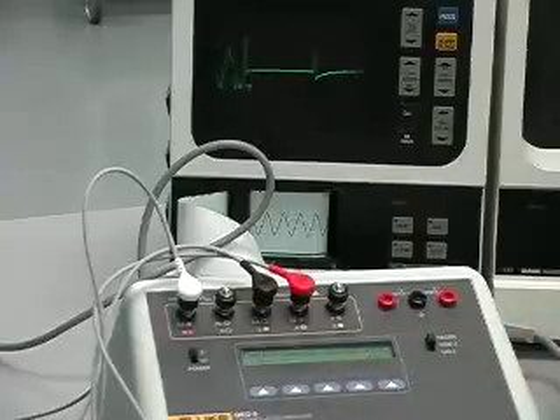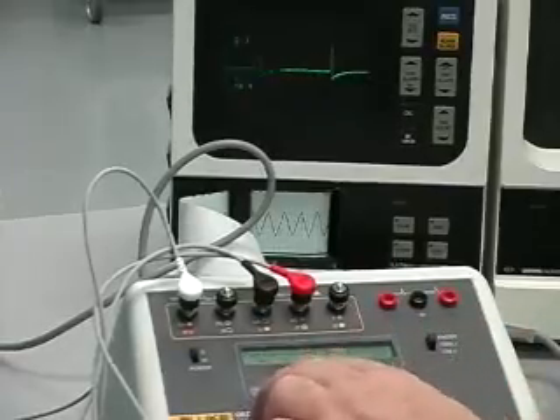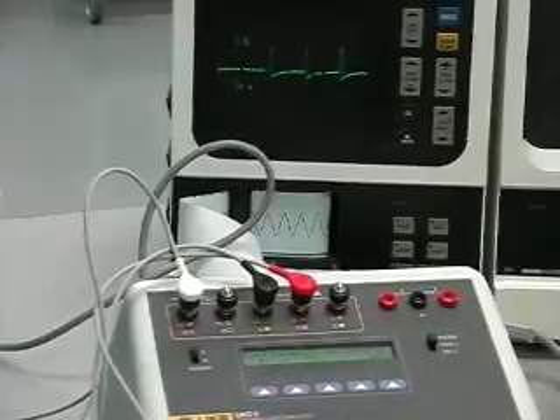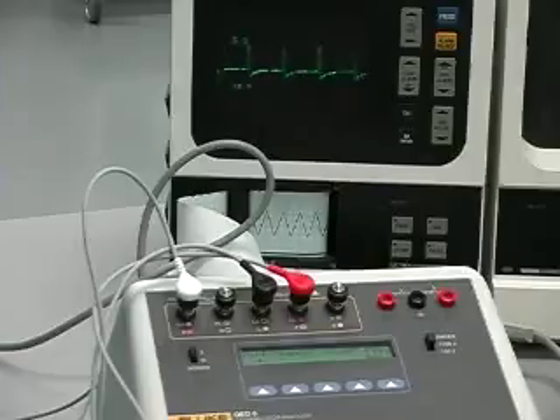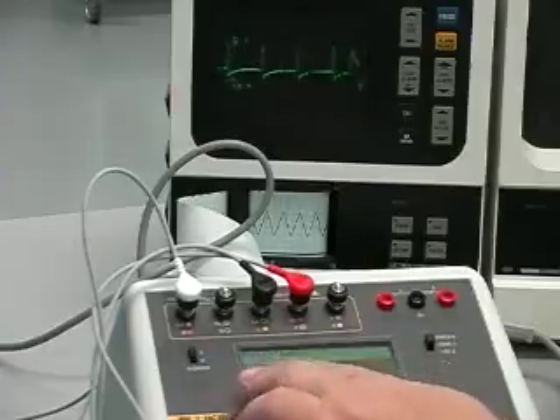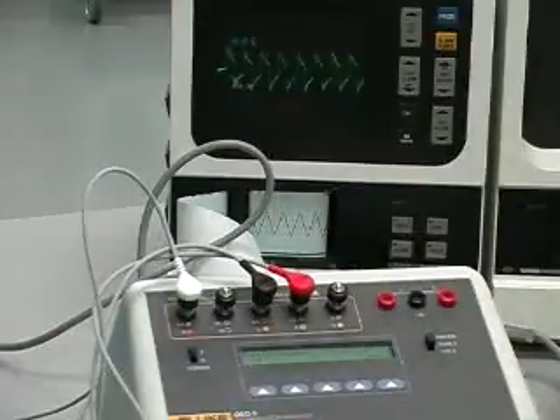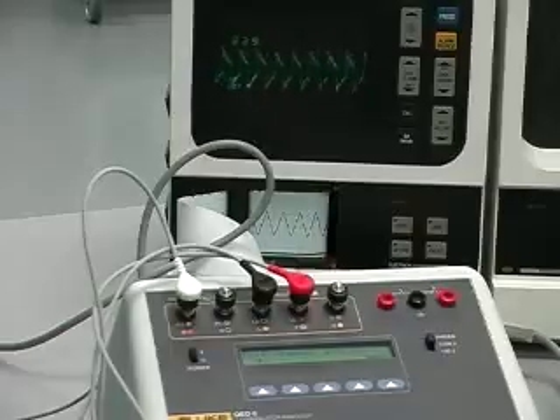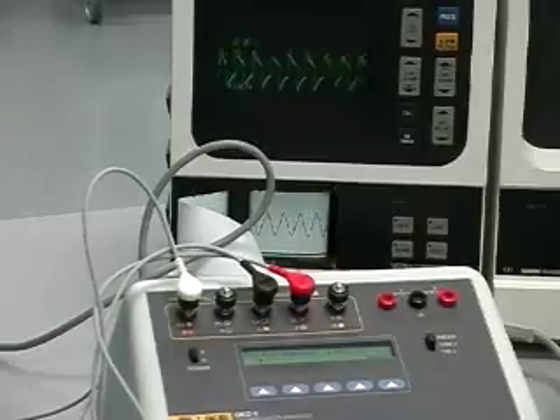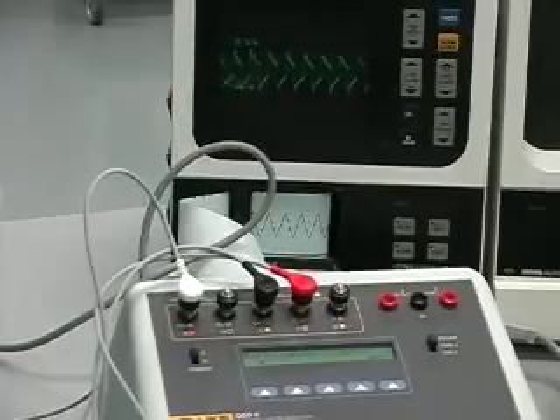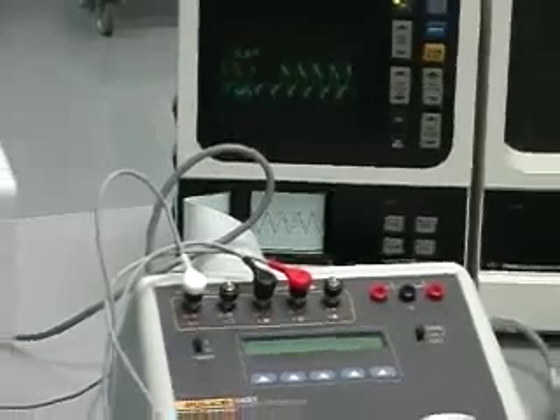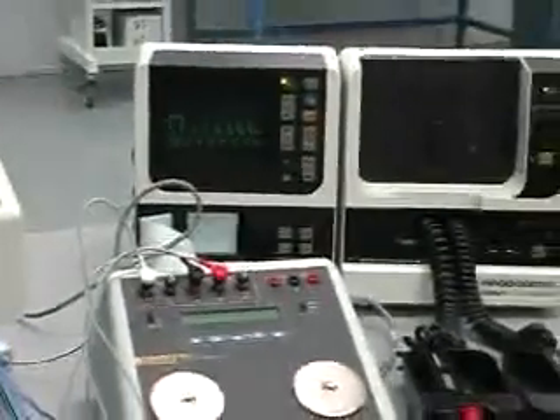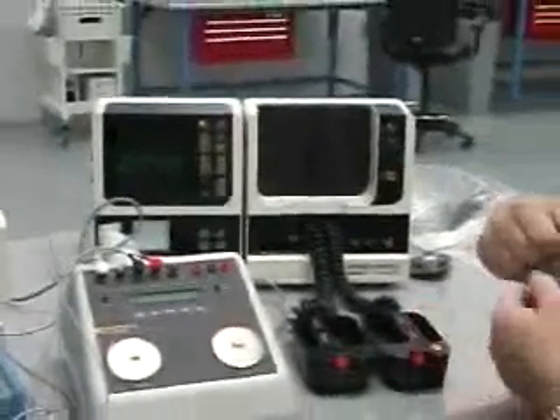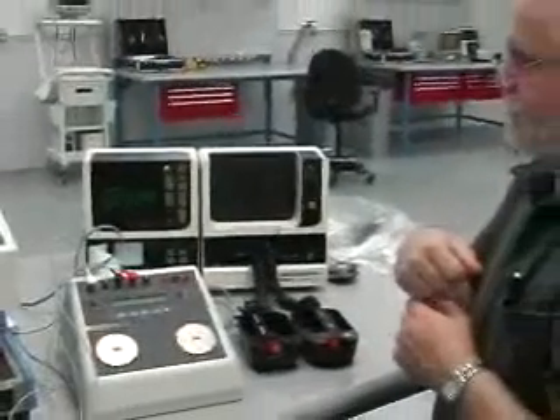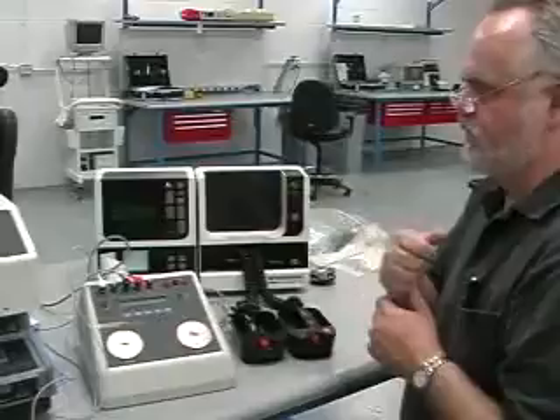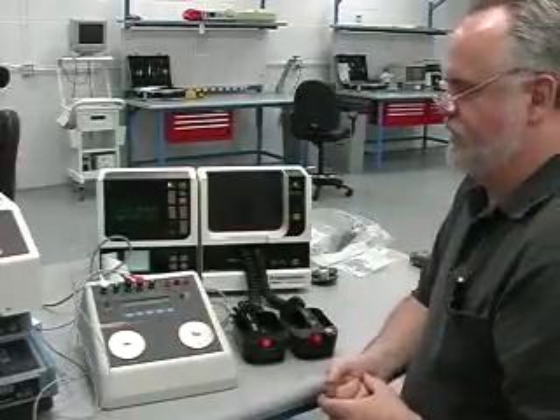And then we're just back to a very basic pulse waveform, at 30 beats per minute and one at 60. So just a quick check, just for looking at a rate meter evaluation. And it then revolves back around to the first square wave. So over the course of looking at the waveform response, using a couple of different waveforms, you're able to get a good handle on the frequency response of the device, the gain and damping adjustments on the recorder, the linearity of the strip chart recorder and monitor, and the ability of the rate meter to work at a wide range of different signals that you will see.